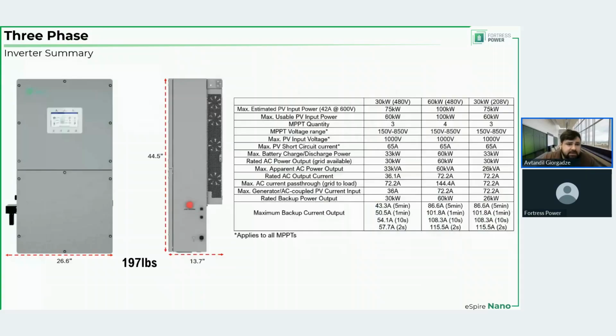So previously, I did show you the inverter, but I did not show its geometric dimensions. Here they are: 26.8 inches from side to side if you're standing in front of it. It is very important to note here, this includes the dongle on the side and the switch, because they kind of stick out from the body of the inverter, but they are included in this width. Height-wise, 44.5 inches, and depth, 13.7. The inverters are around 197 pounds, which is not too surprising considering how much power they pack and how many features. But again, this is a heavy unit. We strongly recommend that no less than 2 people work on installation and maneuver the equipment in the field.